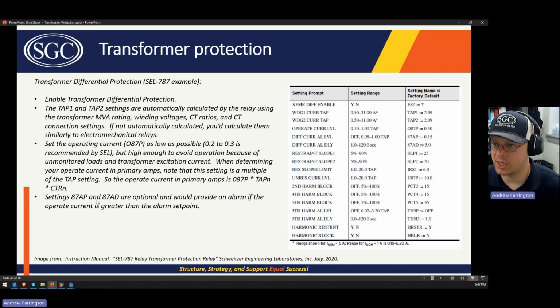These settings for that alarm are what that's intended to cover. It's intended to identify mistakes, or maybe a CT is deteriorating and you're approaching that operate current. So you just want to be aware of that so they can send out somebody to look at it and go, hey, what's going on here, and troubleshoot the problem. So the 87AP setting is the pickup, and then the D is the delay.